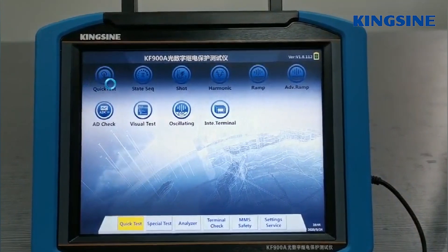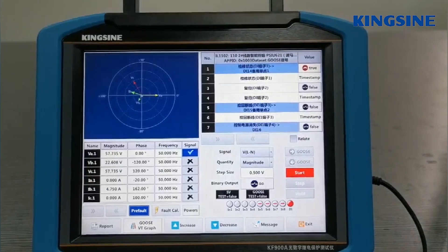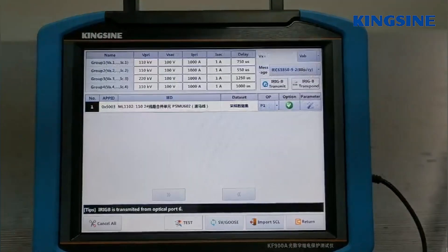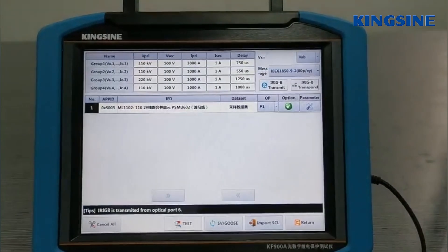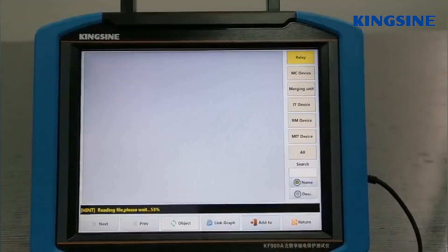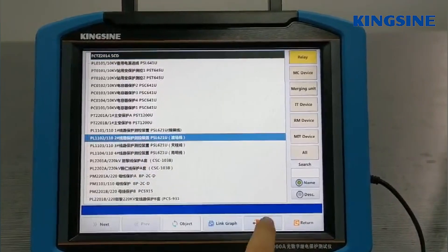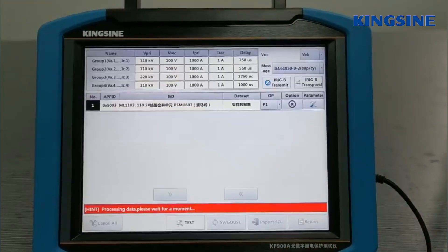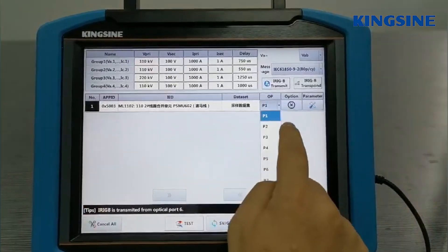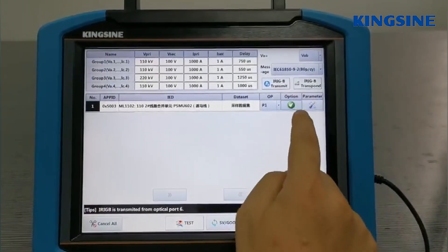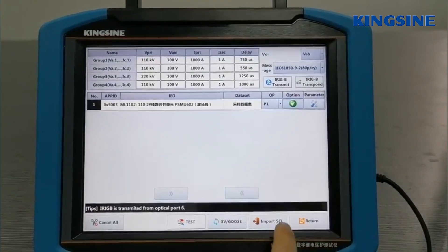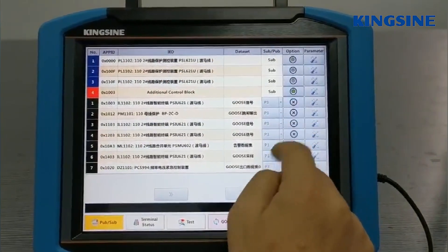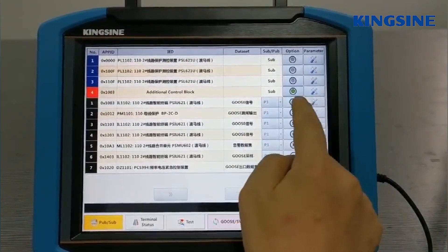Compared to analog relay testing, the only difference is that the SV and GOOSE messages need to be configured first before starting the test. This involves importing the IED, selecting the SV, and subscribing and publishing GOOSE.